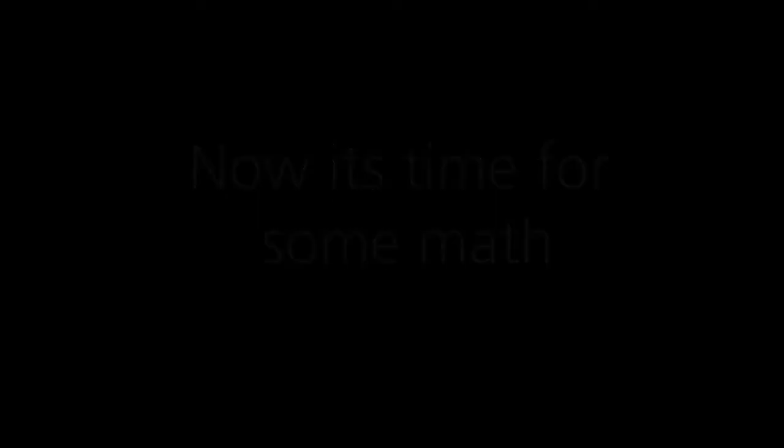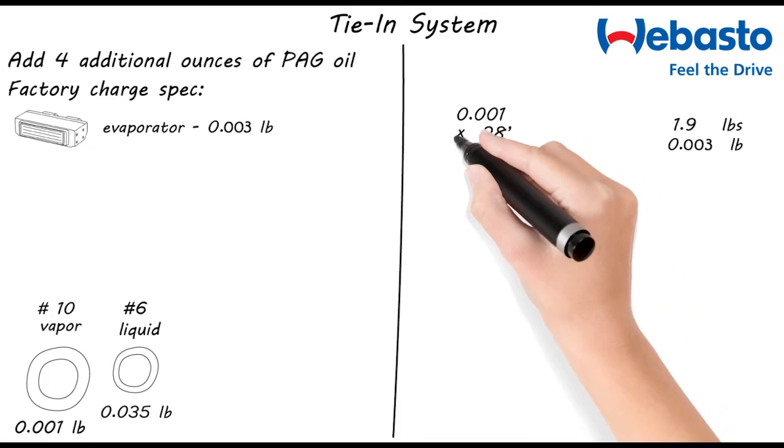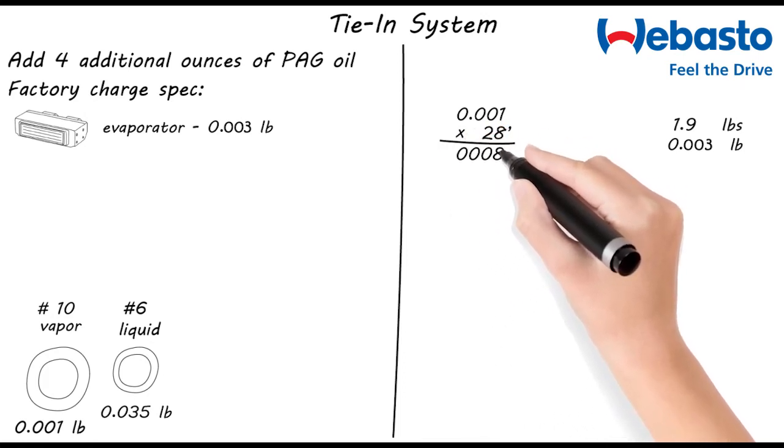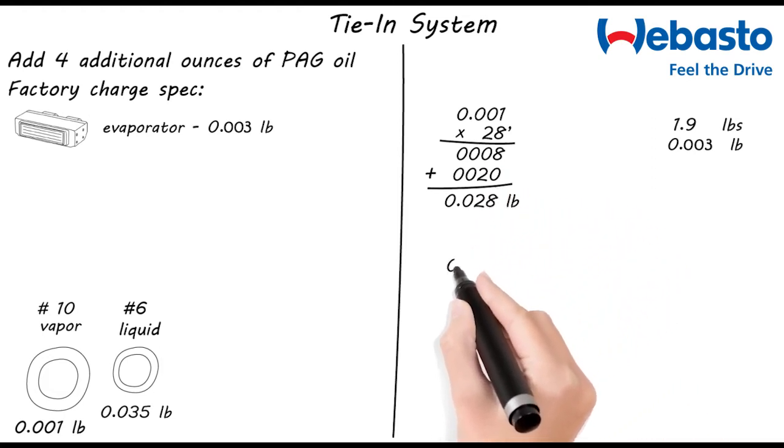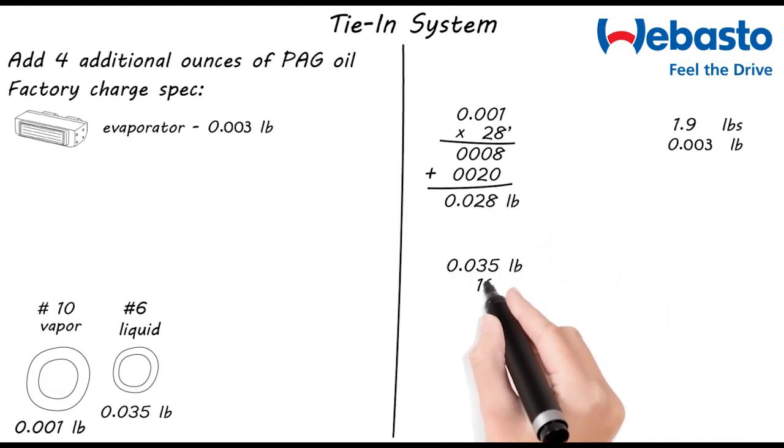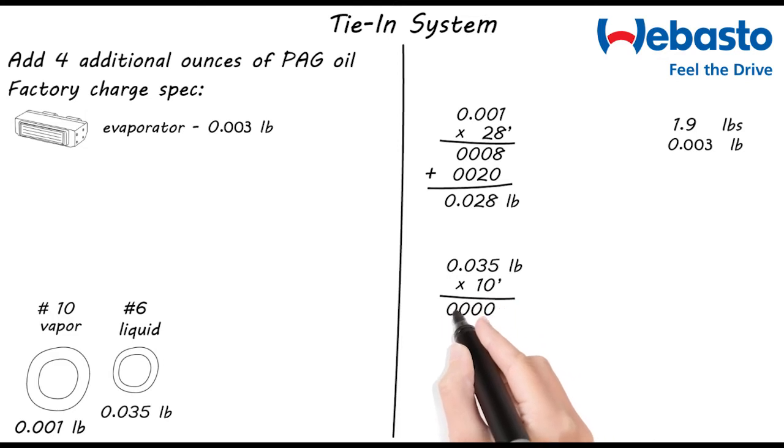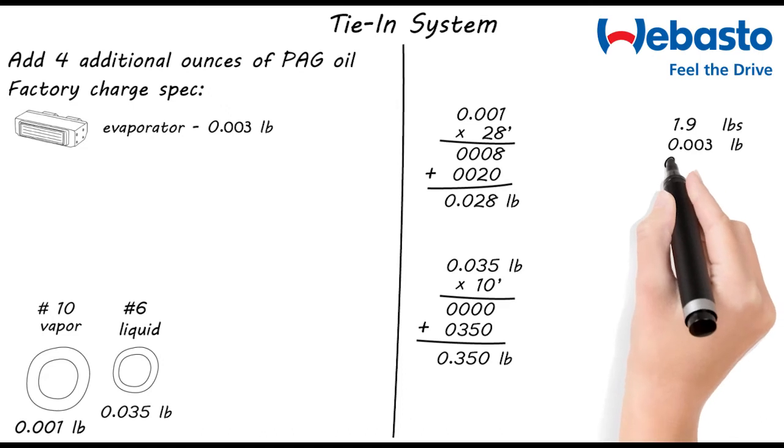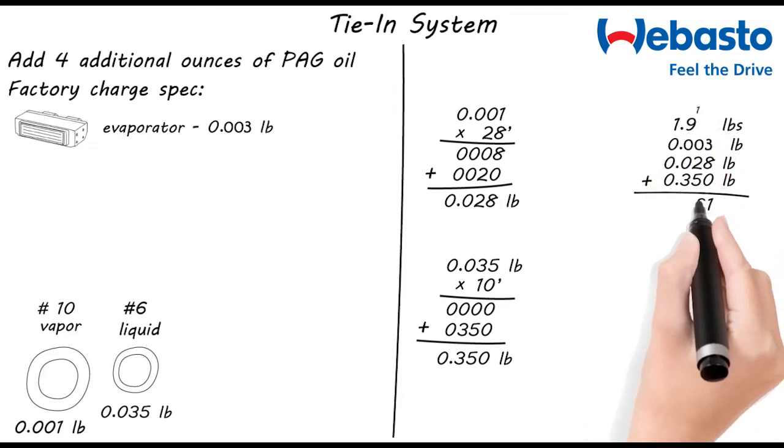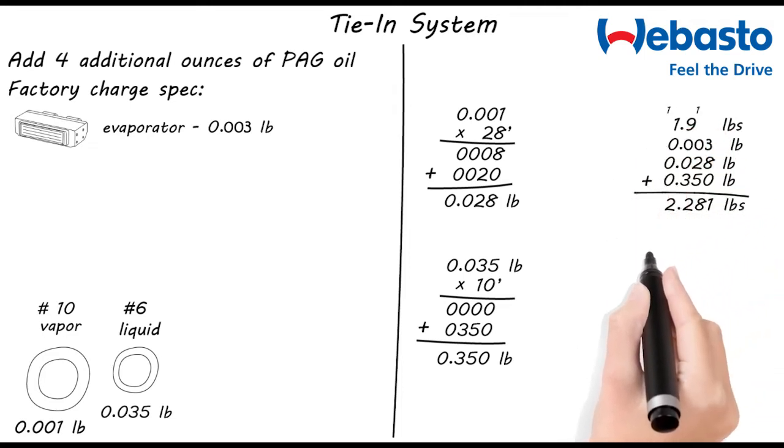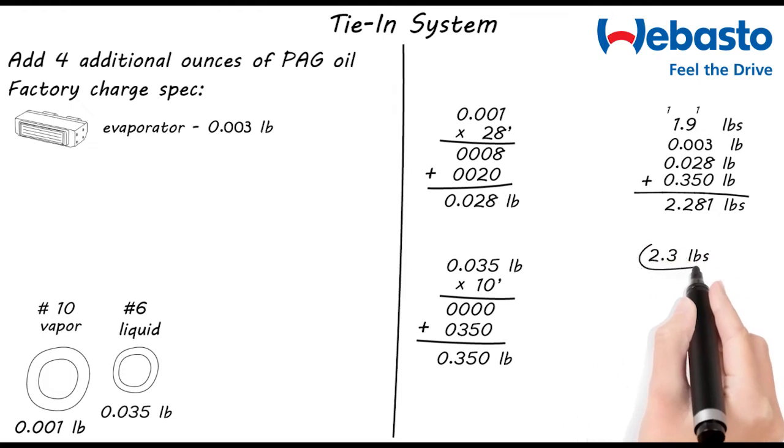Are you ready for some math? Now in our example, we had 28 feet of number 10 hose. So 28 multiplied by 0.001 gives us 0.028 pounds. We also have 10 feet of number 6 line in our installation. Multiplying that out gives us 0.35 pounds of refrigerant. So now we'll take those two values and put them over here and we'll add it all up to figure out our base charge amount. So the math gives us 2.281 pounds. So we'll just round it up to an even 2.3 pounds.